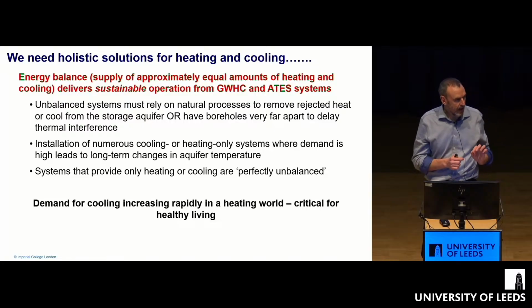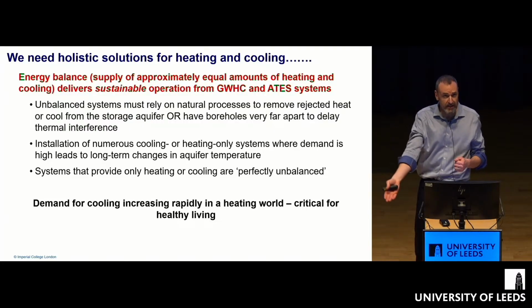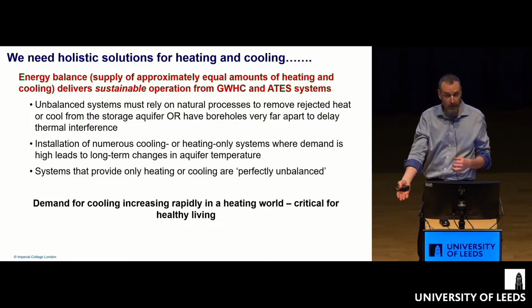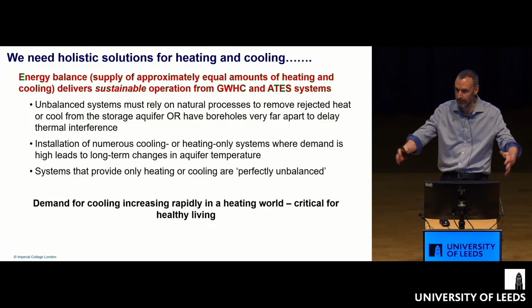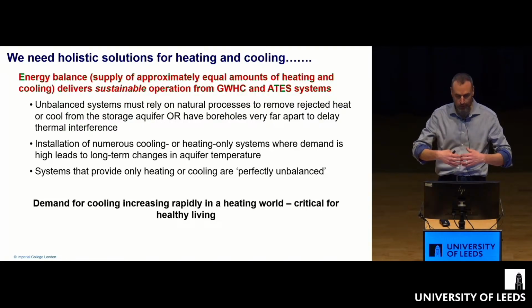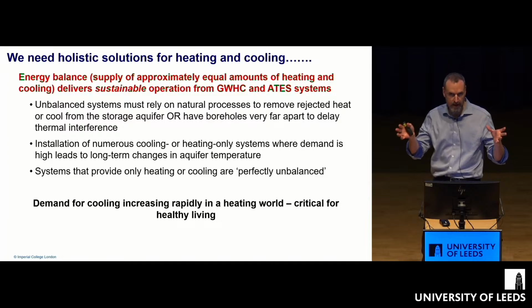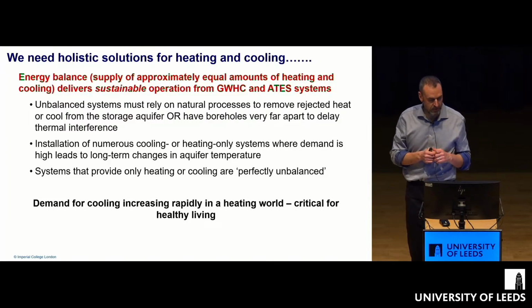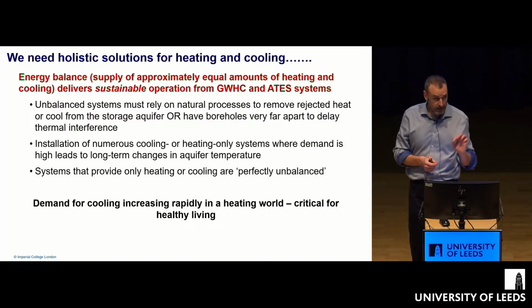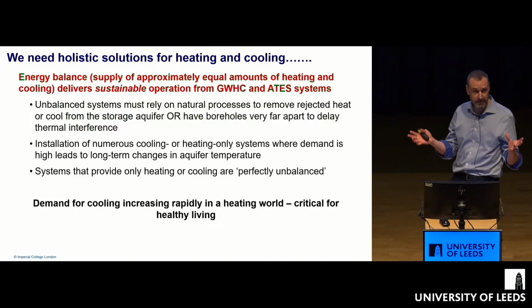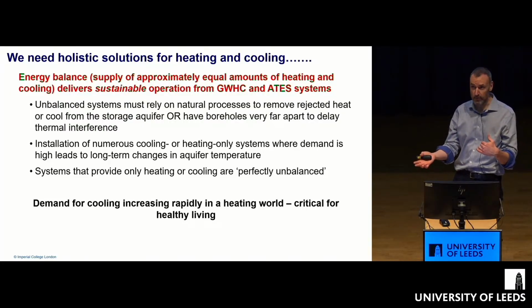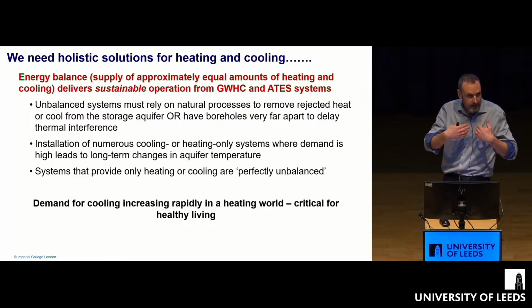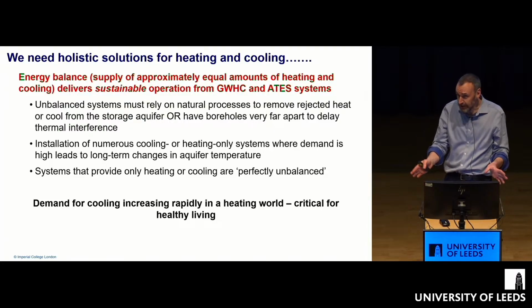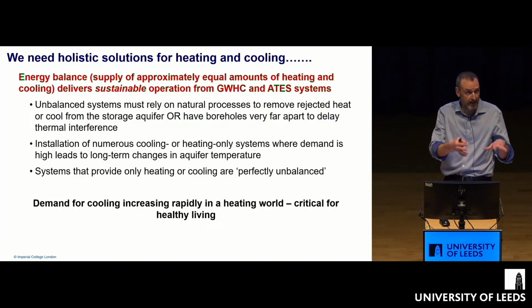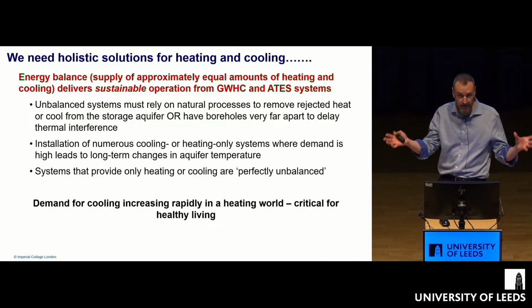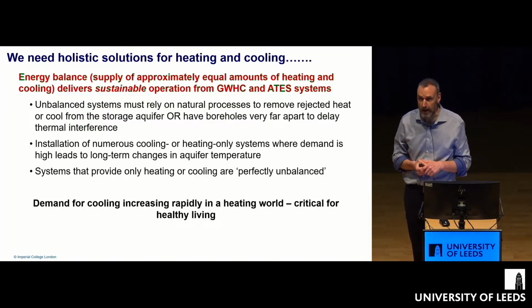If we're very unbalanced and inject lots of waste heat or waste cool, we need natural processes to take that away from the system. Otherwise we get a plume that grows bigger and bigger, and it risks breaking through and contaminating our abstraction wells. The other issue is if we just install lots of systems for heating or lots of systems for cooling, we can start to impose significant changes in the overall aquifer temperature, which can affect our system efficiency and also the efficiency of systems installed by our neighbours.